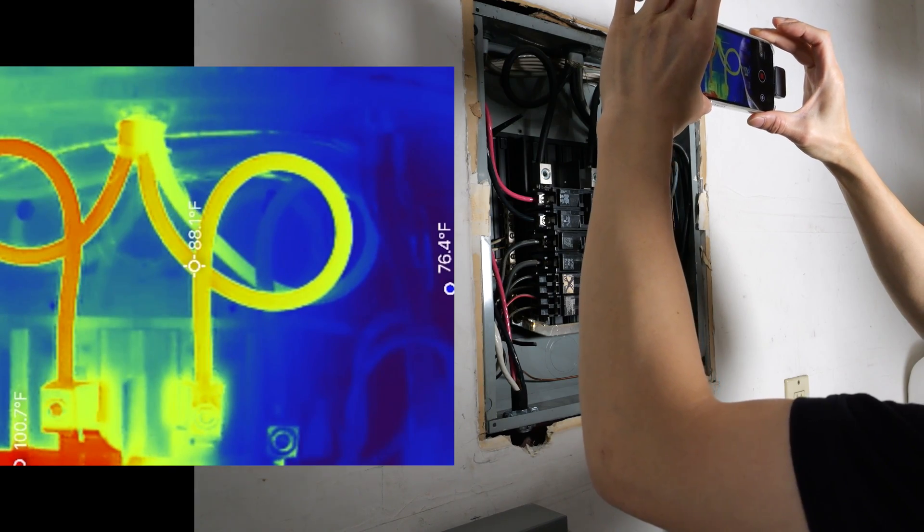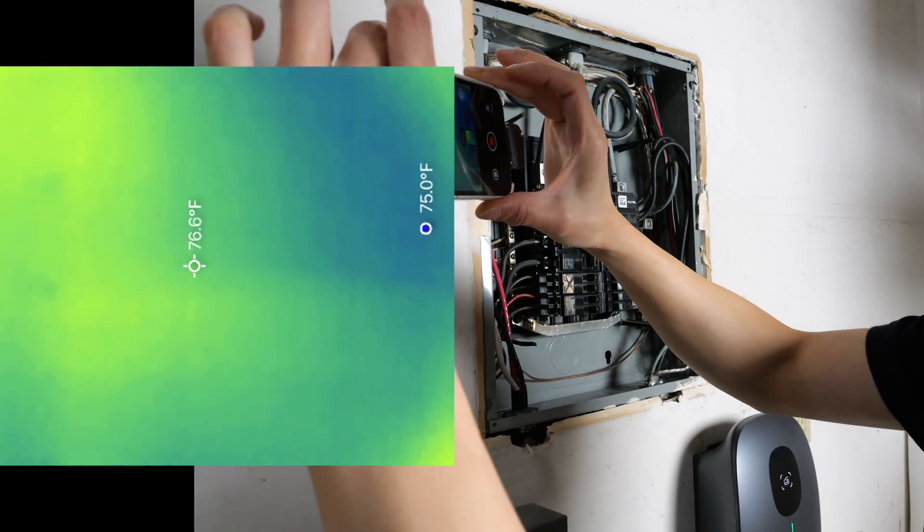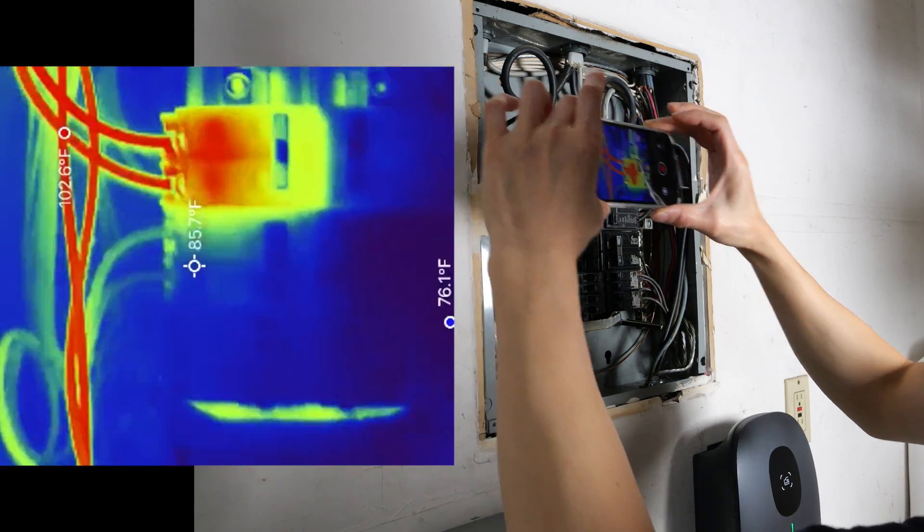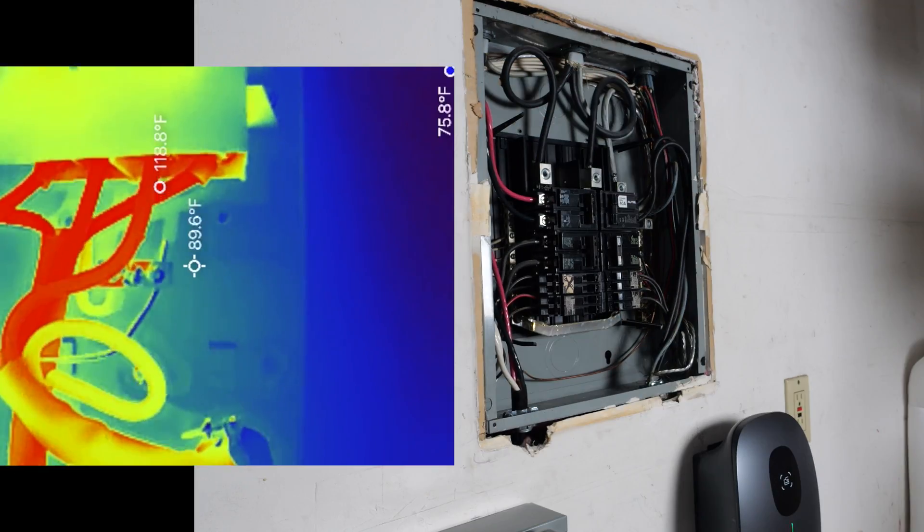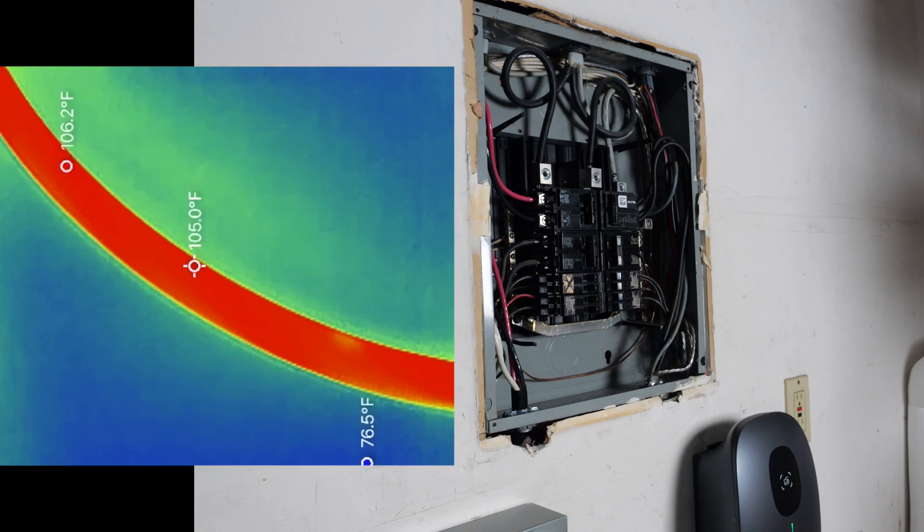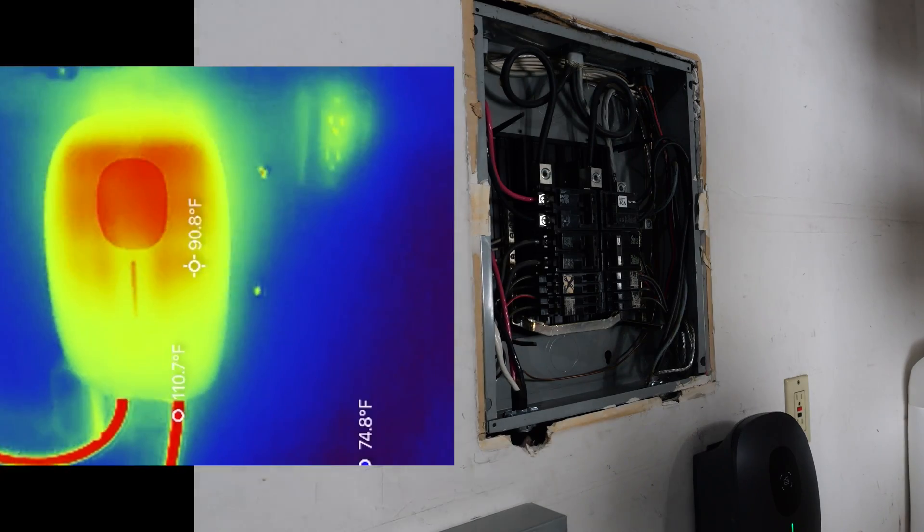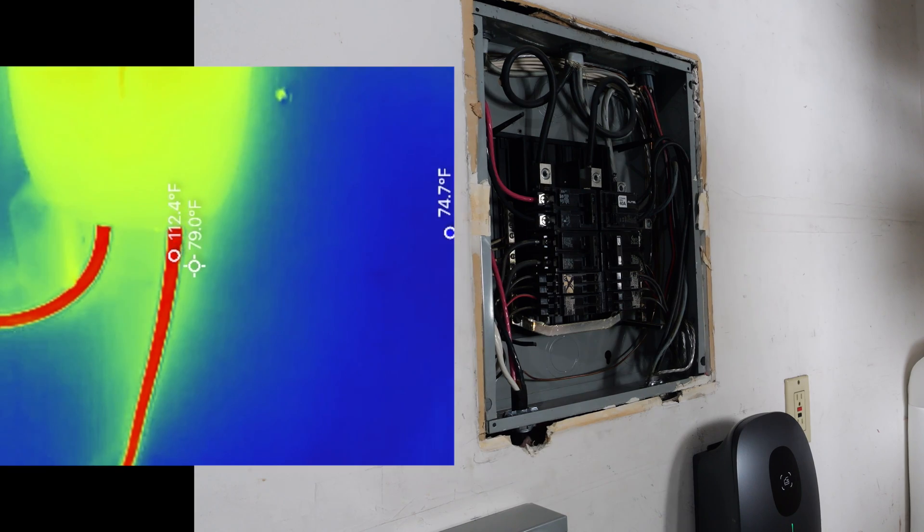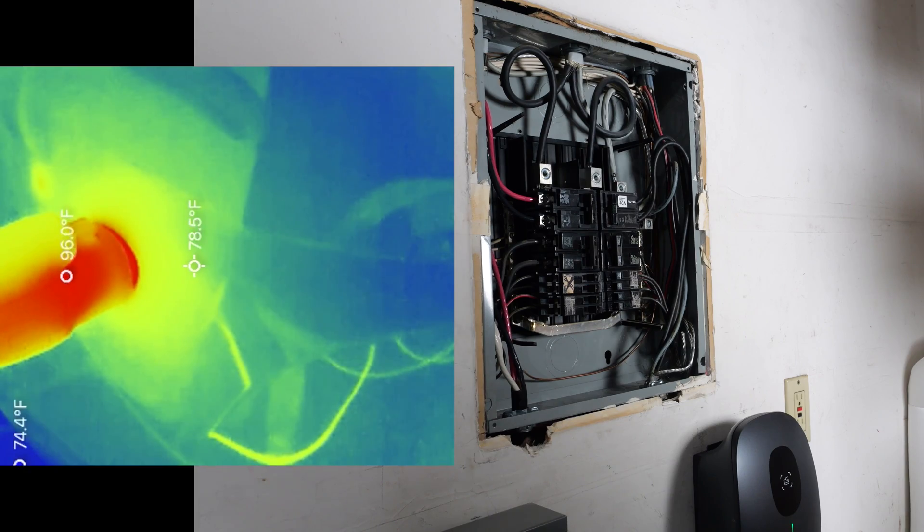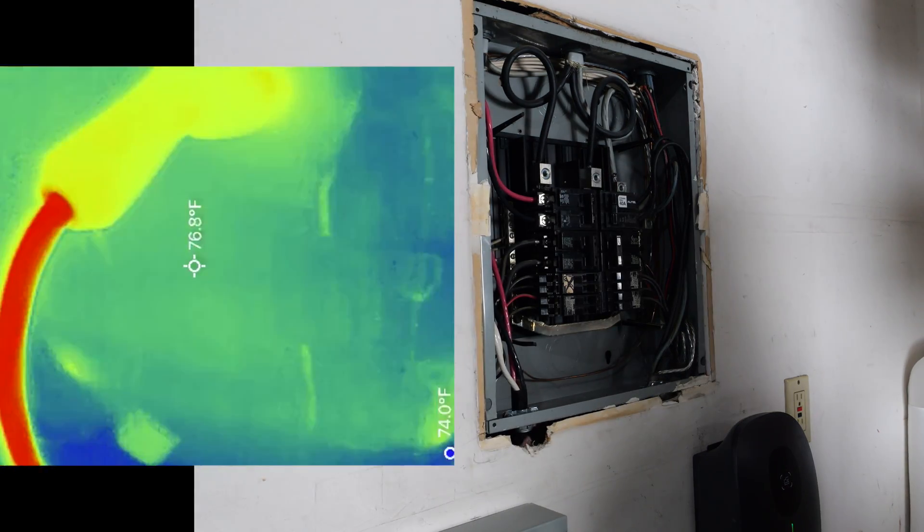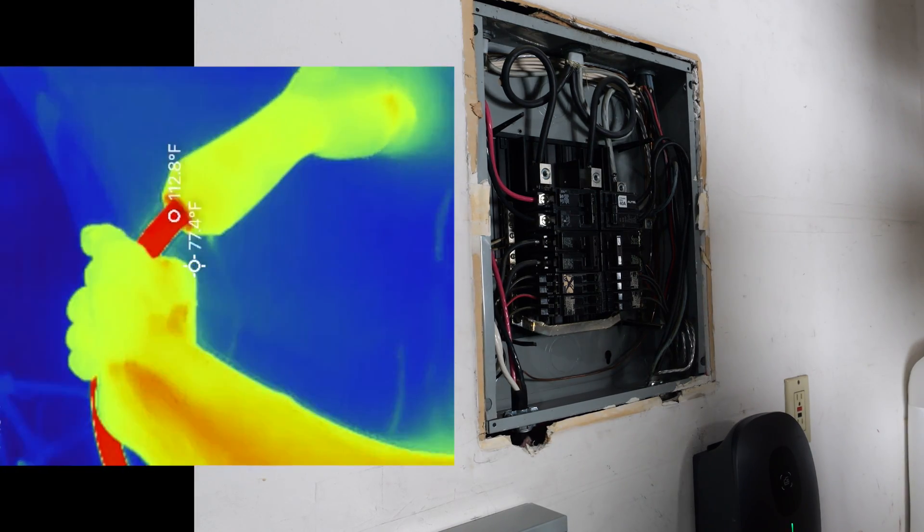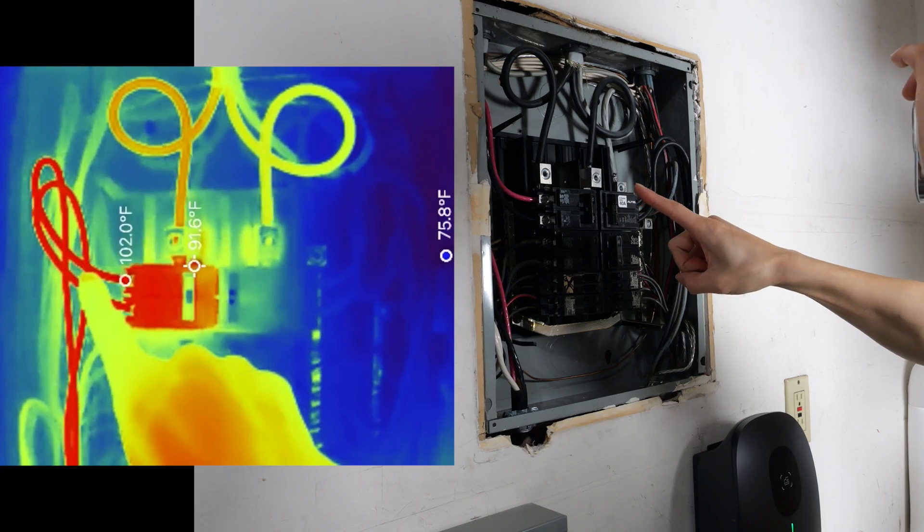The incoming wiring is 88 degrees. Ambient is around 76 degrees and this wire is 105 degrees, which is pretty warm. Inside, these wires are getting a little warmer, 118 degrees. The cable going to the charger is 106 or so. The charger itself, 100. The output wire is a little bit warmer, 112. 112 there. The connector is 95, but we're more interested in the cable here. 113. Touching it, it is a little warm, but not hot. So these wires are relatively thick. Six gauge wires.